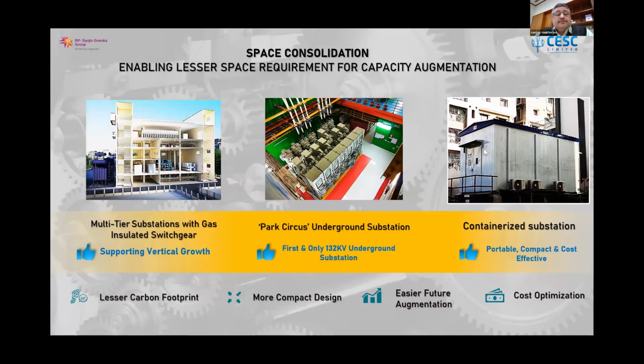In our pursuit of space consolidation, we've enabled lesser space requirements for capacity augmentation. We have standardized our design of multi-tier substations with GIS switchgear - one building housing the 220 kV switchgear, 132 kV switchgear, as well as 33 kV switchgear, all in the same building, taking up very little space.